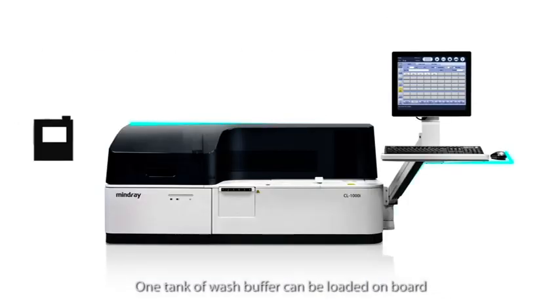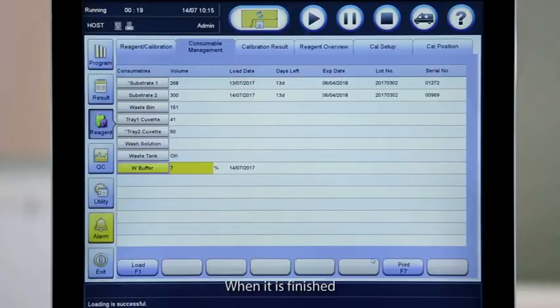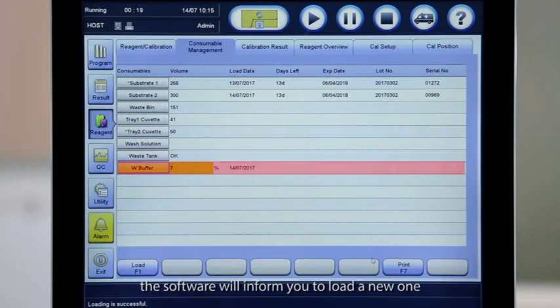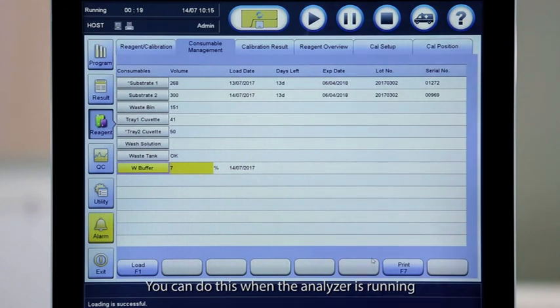One tank of wash buffer can be loaded on board. When it is finished, the software will inform you to load a new one. You can do this when the analyzer is running.